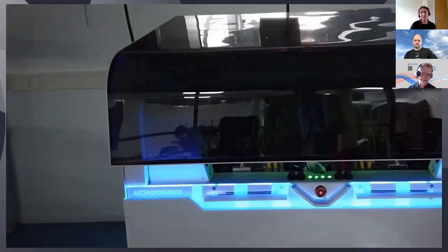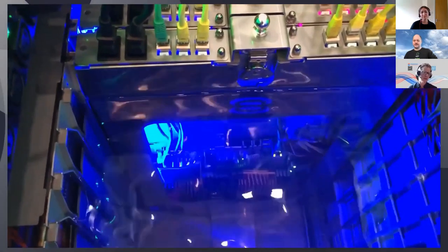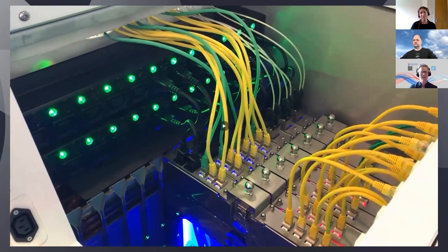Also, you can see the immersion environment here quite nicely in some of the images. The liquid is a dielectric. It's actually a byproduct of a process and is provided by Shell, and itself has really great performance in mechanical terms for cooling, with it expanding and rising as it heats. But also, it doesn't have any issues with global warming potential. It's not volatile. It doesn't evaporate. You don't lose it when you open the lid. In terms of the life and cost, but also in terms of its environmental credentials, it's really quite a great solution in that way too.